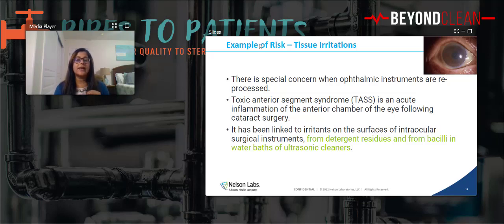But one thing I found very interesting when I was researching was detergents and residues from bacilli in water baths of ultrasonic cleaners. These instruments are usually cleaned in ultrasonic cleaners, and detergent residuals from the ultrasonic cleaners can cause that, right? So it's important to understand it's not just the instruments, but also the equipment that we're using to process these devices, like I said, the AERs, the washer disinfector, the ultrasonic cleaners that I just talked about, that can cause these irritations to the eye.